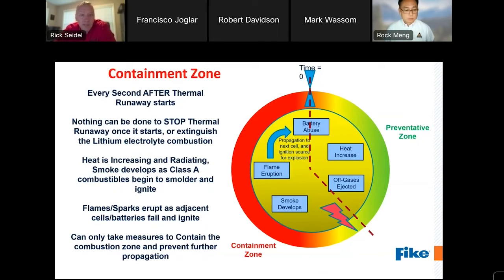The containment zone is every second after thermal runaway has begun. There does not yet exist a system or extinguishant that is proven to suppress or stop thermal runaway once it has started. You can only take measures to try to contain it as best as possible to prevent further propagation amongst adjacent cells or surrounding combustibles.